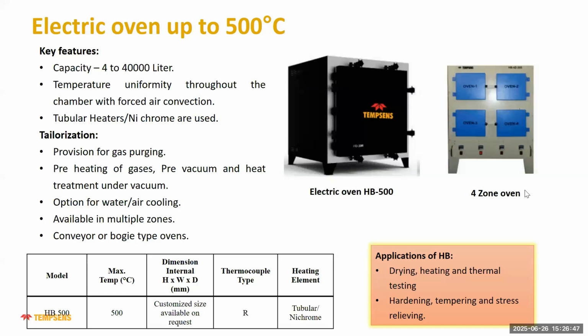And temperature uniformity we can provide by forced air convection. So we basically use an air circulation fan on the top or maybe on the side to get the uniform temperature completely inside the oven, because at lower temperature radiation heat is less, so we have to get the uniform temperature only by air convection. That's why we use a special type of fan to get the uniform temperature completely inside the furnace. And for the oven we can also provide gas purging, preheating, under vacuum, water or air cooling, multiple zones, and conveyor or bogie type ovens can also be provided. So you can see the pictures, an electrical oven with 500 and then a complete 4 zone.